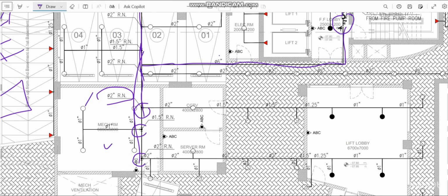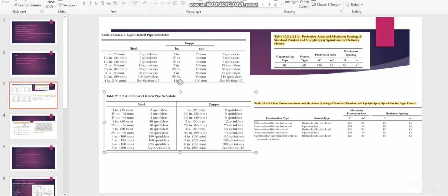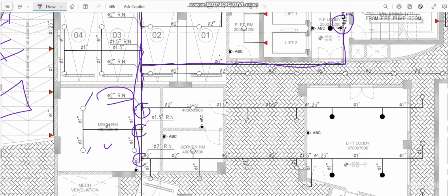So we have one sprinkler and one sprinkler here. If you go to the schedule as per NFPA 13, here you can see ordinary hazard. A 1 inch pipe can cover a maximum of 2 sprinklers. A 1.25 inch pipe, 32 mm, maximum 3 sprinklers. 1.5 inch, 5 sprinklers. Now you can go to the drawing. So here you can see 2 sprinklers, so we have a 1 inch pipe. So at this point it is 4 sprinklers.